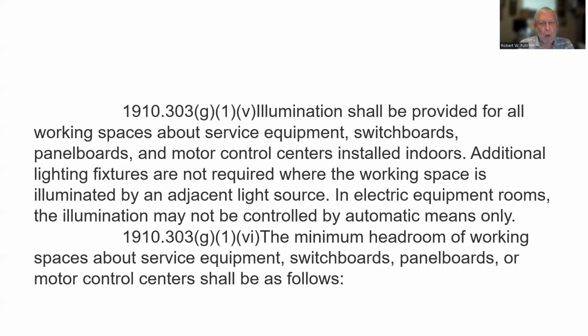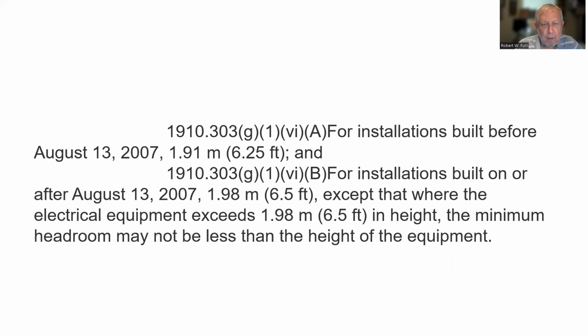Illumination shall be provided for all working spaces about service equipment, switchboards, panel boards, and motor control centers installed indoors. Additional lighting fixtures are not required where the working space is illuminated by an adjacent light source. In electrical equipment rooms, the illumination may not be controlled by automatic means only. Interesting. The minimum headroom of working spaces about service equipment, switchboards, panel boards, or motor control centers shall be as follows. Here you go again.